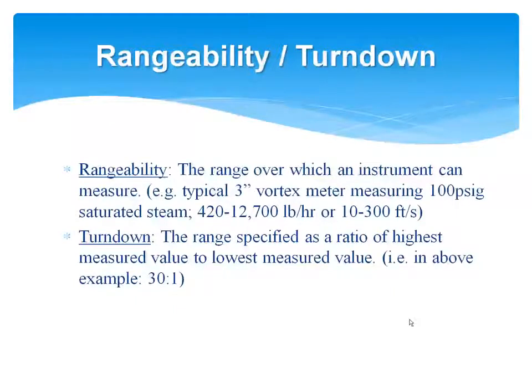Rangeability and turndown are another real critical component of meter selection. The rangeability of a meter is simply the range over which it can measure. So we've got an example here of a meter that measures from roughly 400 to 13,000 pounds per hour. And then you've got some velocity numbers there as well, from 10 to 300 feet per second. Well, turndown is nothing more than the ratio of the high and low limits of the range. So again, in our example, you've got a 30-to-1 range.